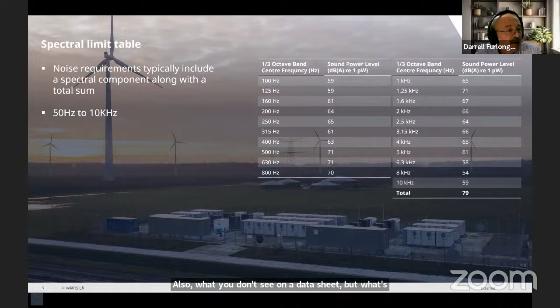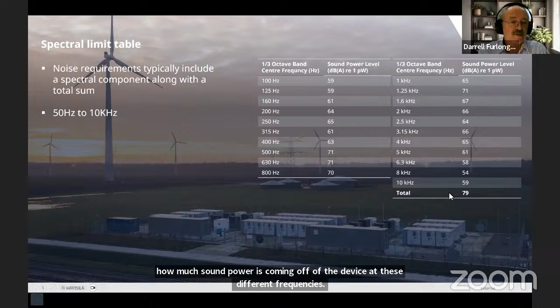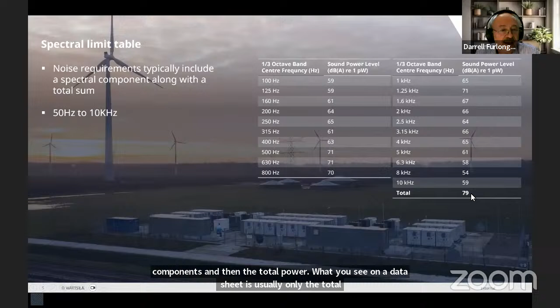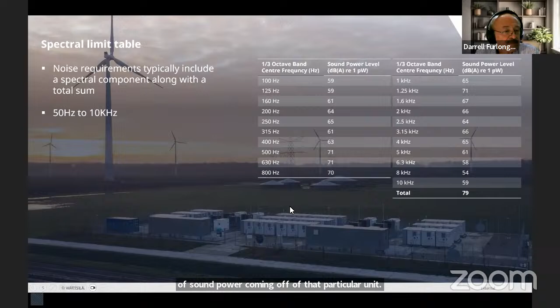Also, what you don't see on a data sheet, but what's important, is the spectral content of the noise. Usually between 50 hertz, 100 hertz, up to 10 kilohertz are the frequencies of interest. What I show here is a table, just an example measurement that we did on a piece of equipment in our lab, showing how much sound power is coming off of the device at these different frequencies. While we have an upper limit, here I show 79 dBA, which is what all this would add up to as one limit, you also have requirements for each frequency that you typically need to meet. So, spectral components and then the total power. What you see on a data sheet is usually only the total amount of sound power coming off of that particular unit, but you also want to keep a look at the spectral content.